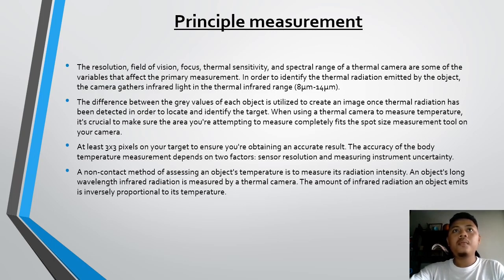Resolution, field of vision, focus, thermal sensitivity, and spectral range of the thermal camera are some of the variables that affect the primary measurement. In order to identify the thermal radiation emitted by an object, the camera gathers infrared light in the thermal infrared range of 8 to 14 micrometers.